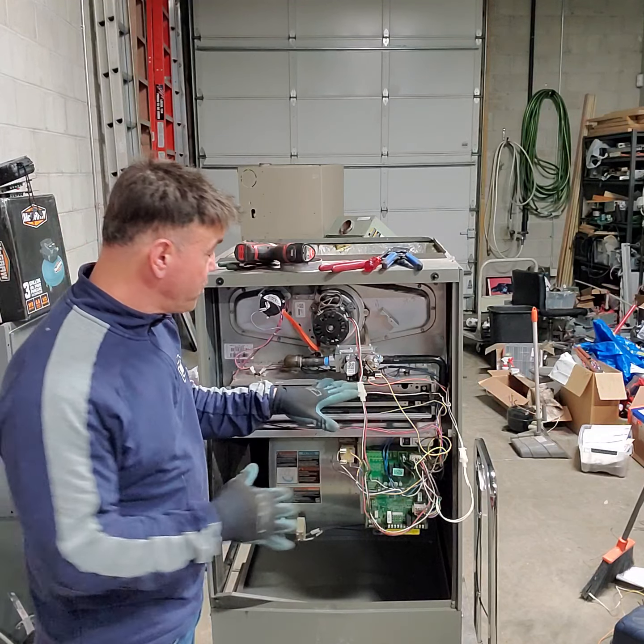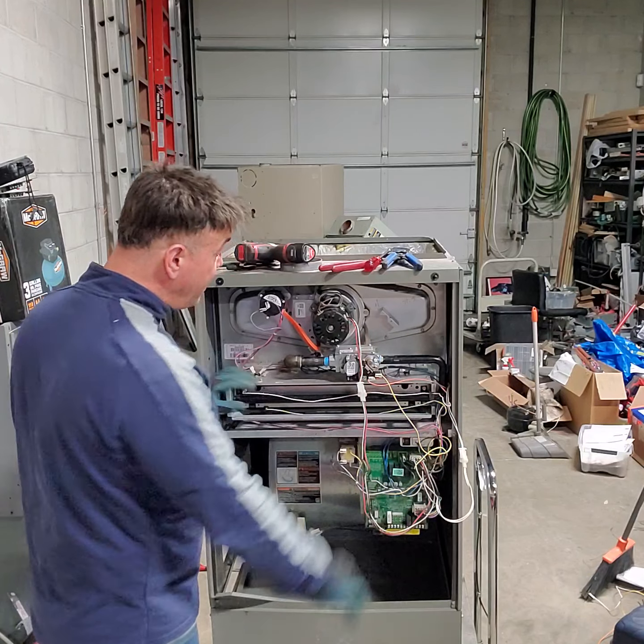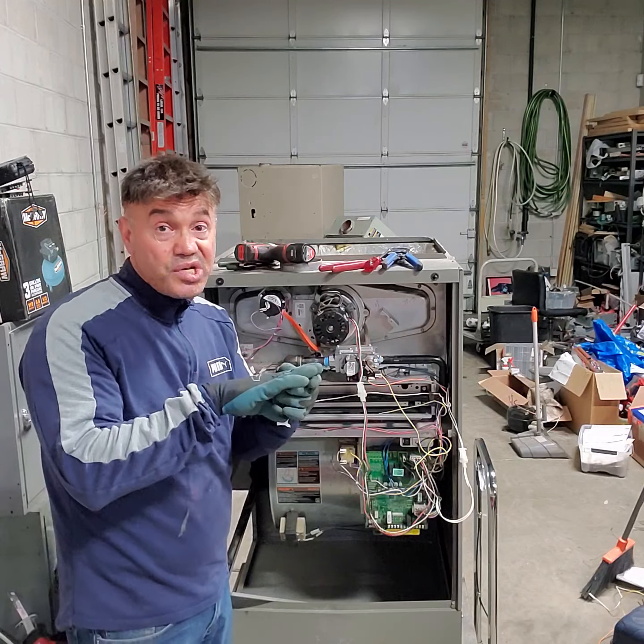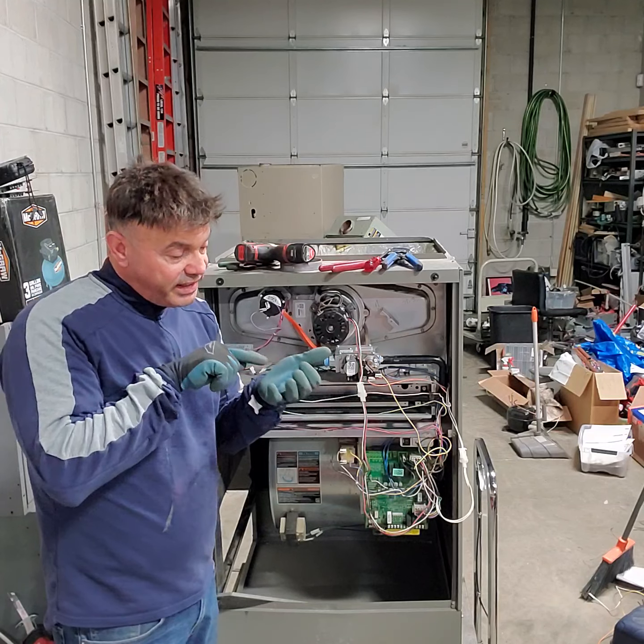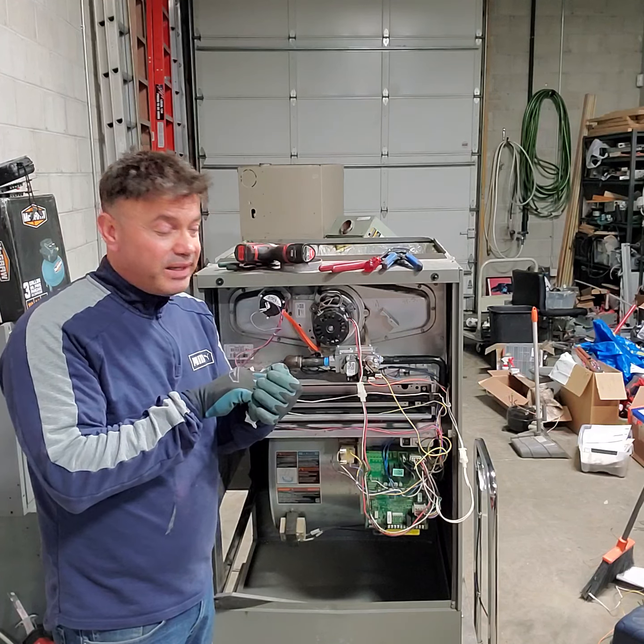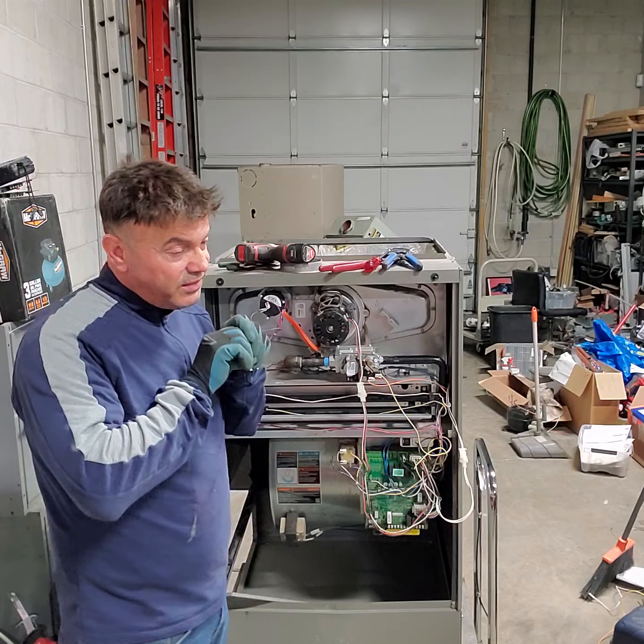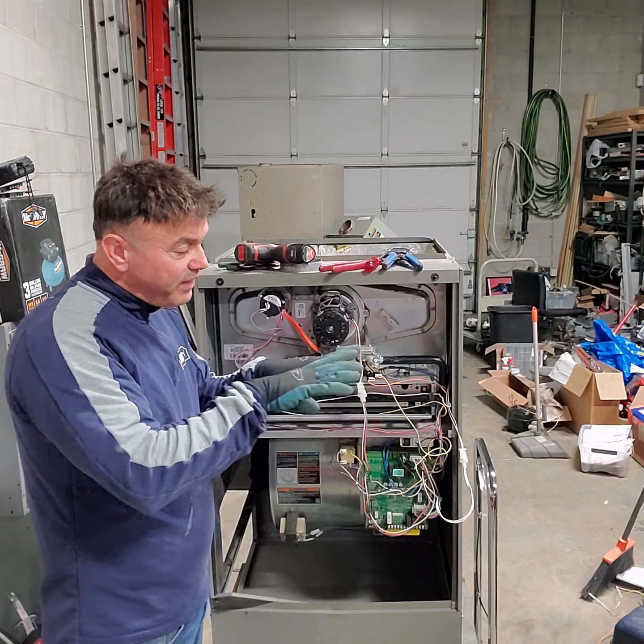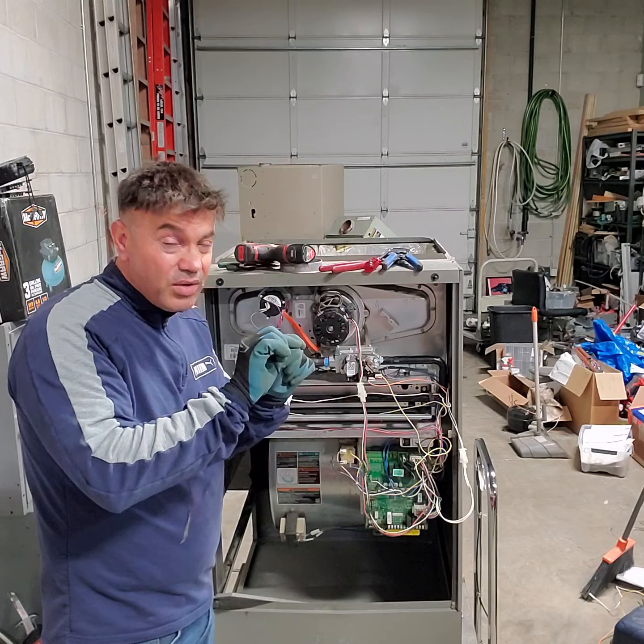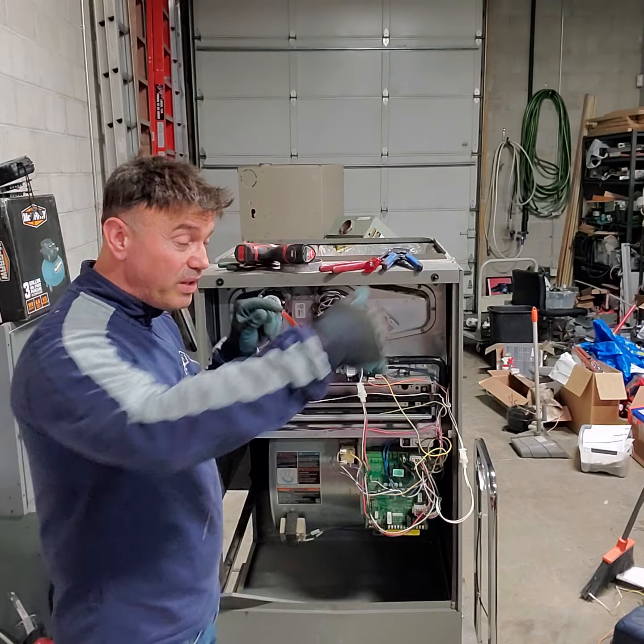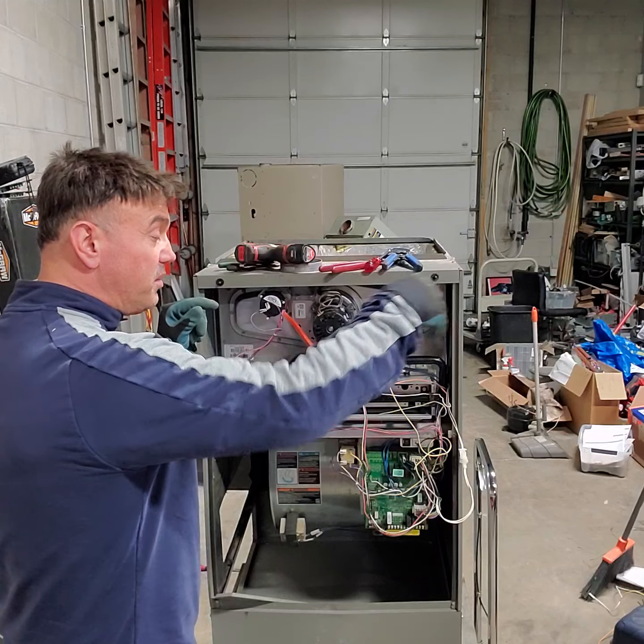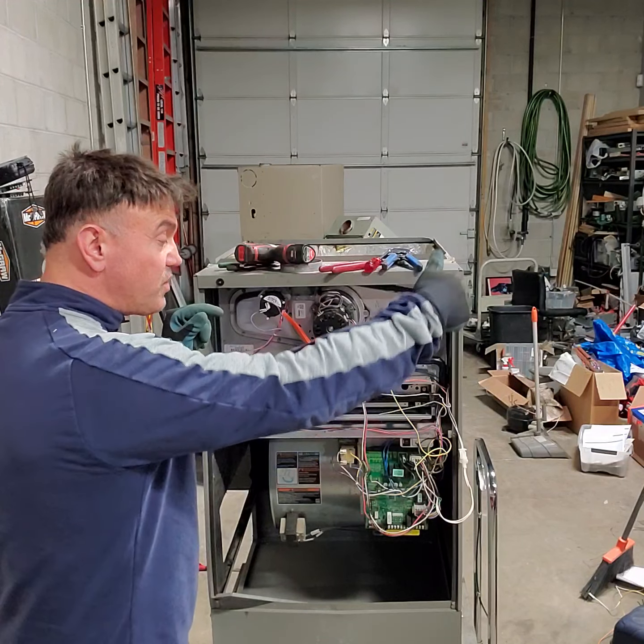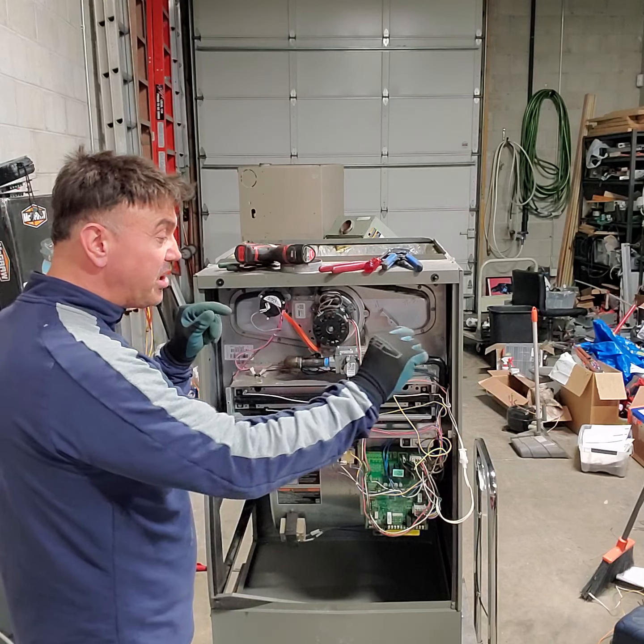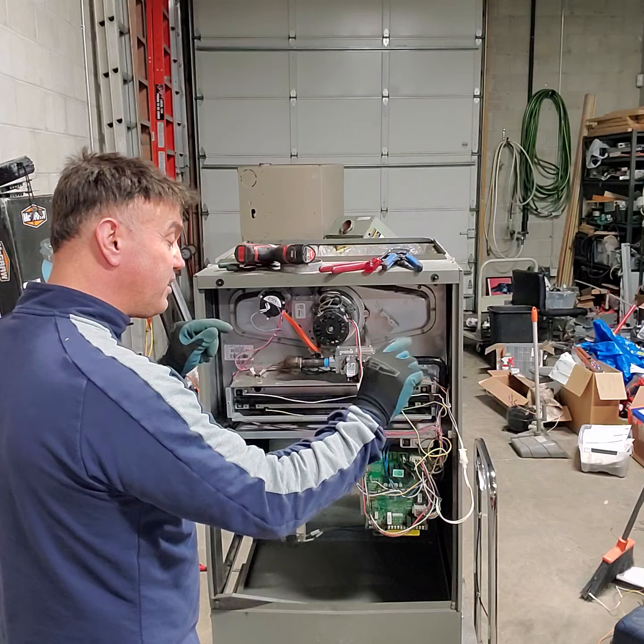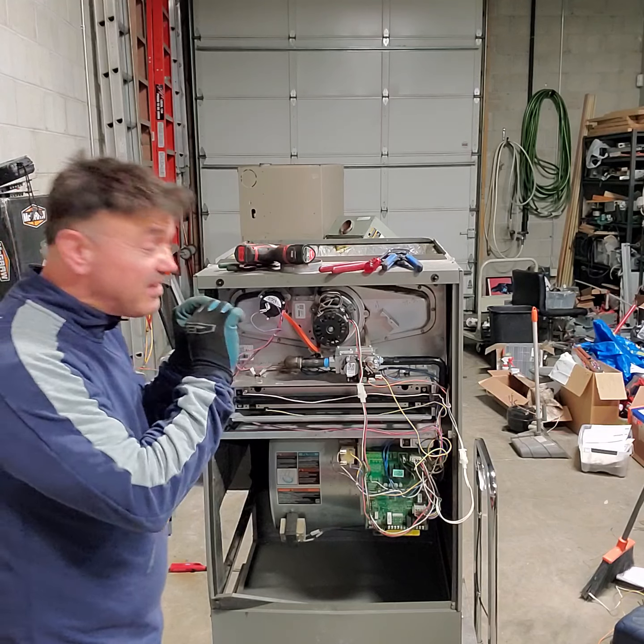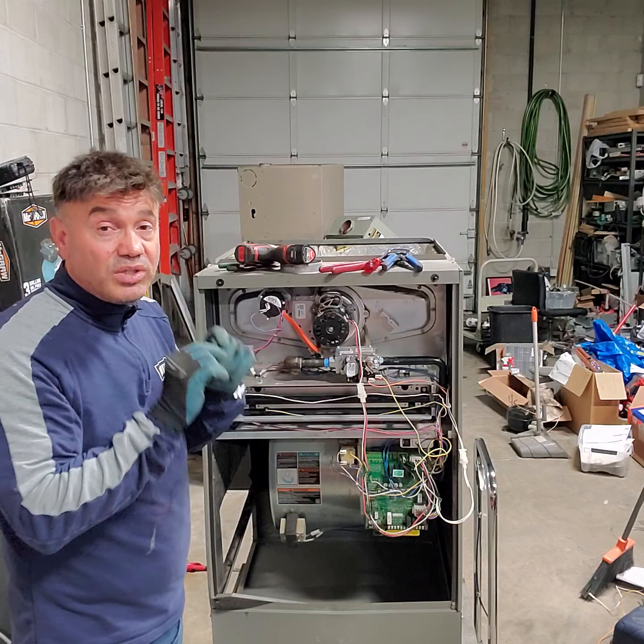I'll have another video to show you in detail the burner compartment. But inside here there are injectors, like a flange where the gas goes in. It looks like an airplane wing, and the gas is distributed over it. Every flange of these small ones is connected somehow together, so when the ignition ignites one of these fire chutes or injectors, they have a path so they can ignite each other in sequence, taking fire from each other. Sometimes that very tiny path is clogged with dust.